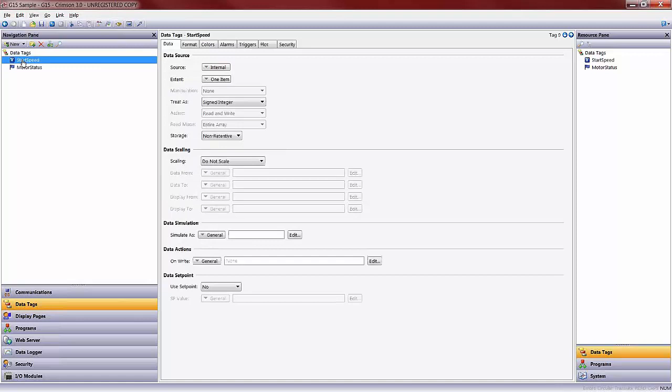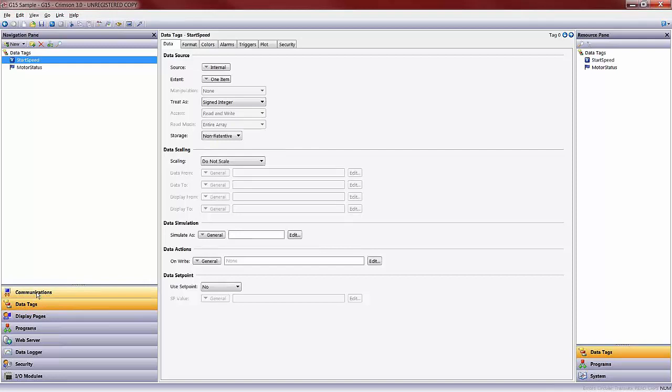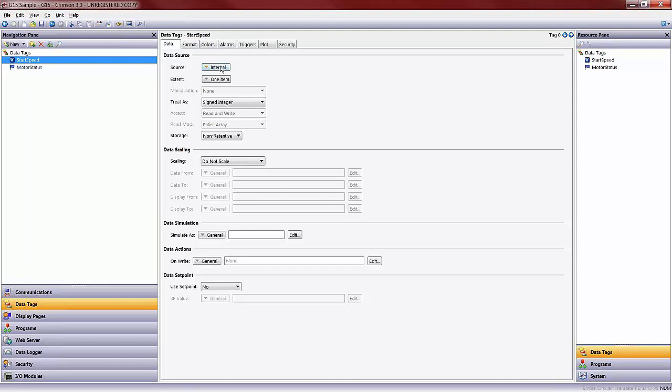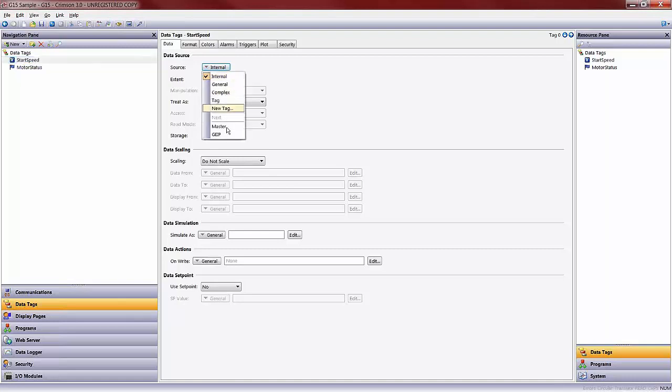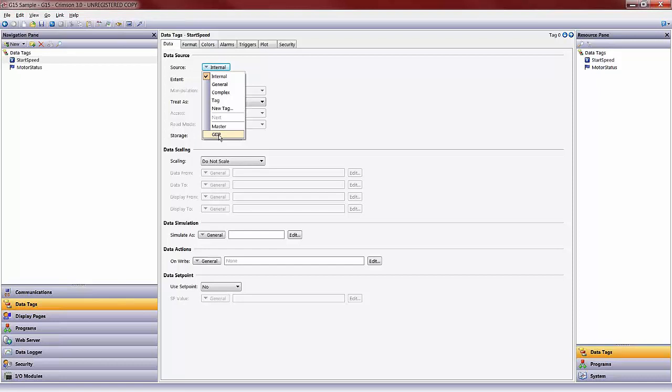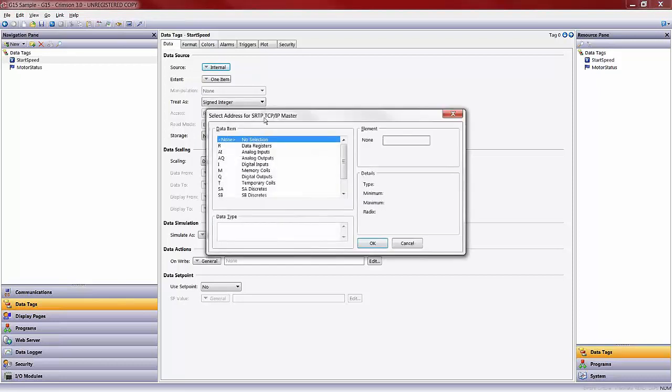In order to map this to the GE IP controller address that we're communicating to in the communication section, I'll click on either tag and go to the data tab in the editing window. Under data source, source, instead of being an internal tag, which is what the blue indication means, internal to the Red Lion device only, I click on internal and select the item I want to communicate to. In my case, I only have one selection, which is the GE IP controller. If I had added more protocols in my communication section, I would see all of the controllers that were available to map to here.